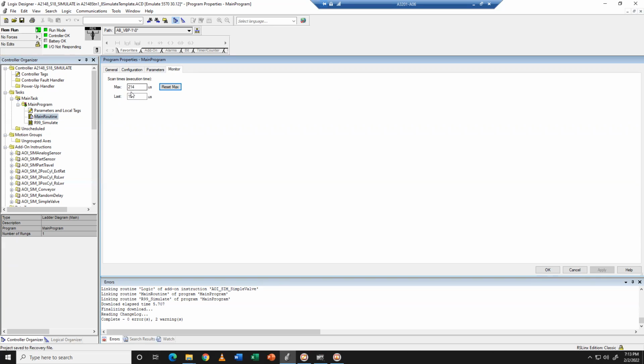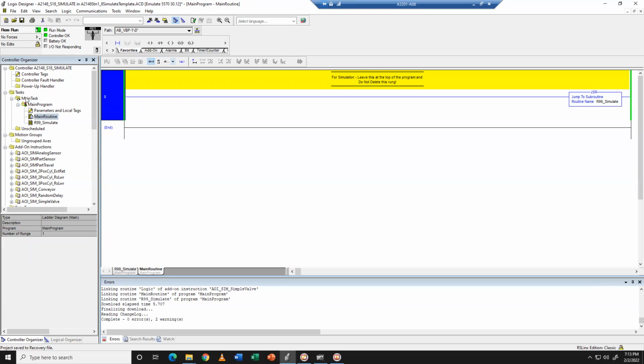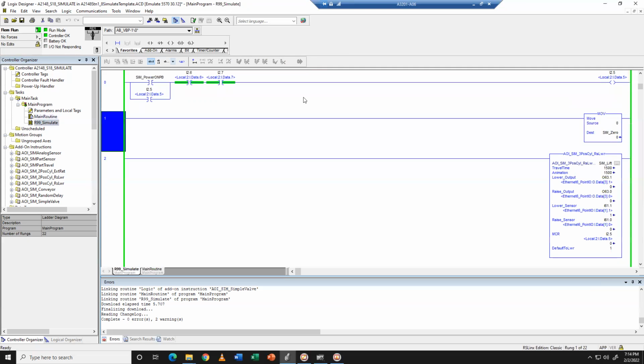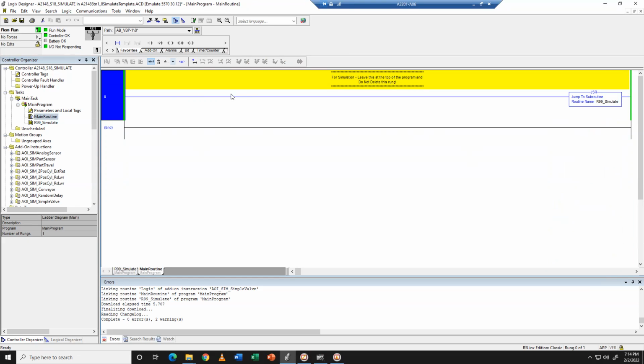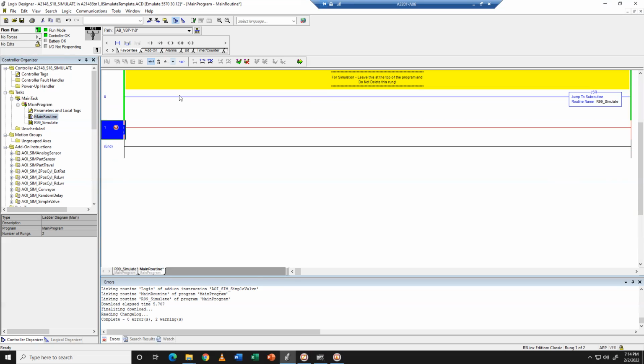And the monitor here, you can watch and see how long scan times take. So the processor is going to go through, run your main routine. Inside this main routine, we have a jump to subroutine, which jumps over to R99 simulate, and then it'll run all of this logic. We're going to ignore the logic for today, and we're going to be putting our code changes in main routine, but don't touch rung 0. Don't delete it. You can do your edits above it or below it. It doesn't matter. Just don't delete rung 0 with the jump to subroutine. Other things won't work.